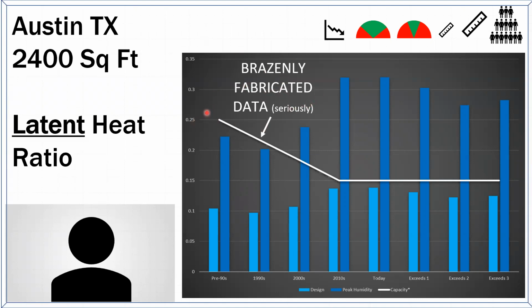But if you ask what has happened to modern high efficiency equipment, particularly at the cheaper end of high efficiency equipment, if you look at the actual performance data, newer, more efficient equipment spends less of its energy on moisture removal and more on temperature control. It's pretty difficult to find a unit out there with below 80% sensible heat ratio that spends more than 20% of its energy controlling moisture. Whereas it was a lot easier to find that back in the day, because low efficiency systems, like R22 systems with small coils, got colder faster than modern systems.